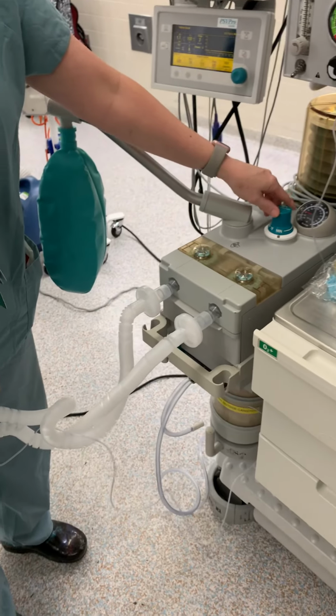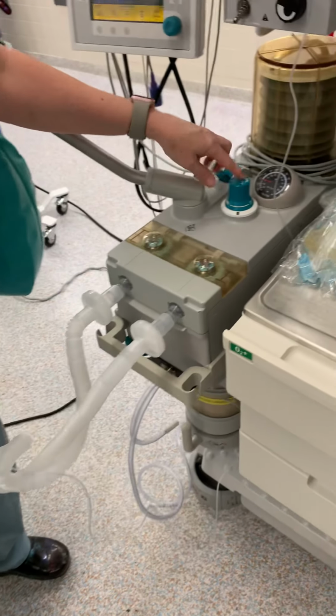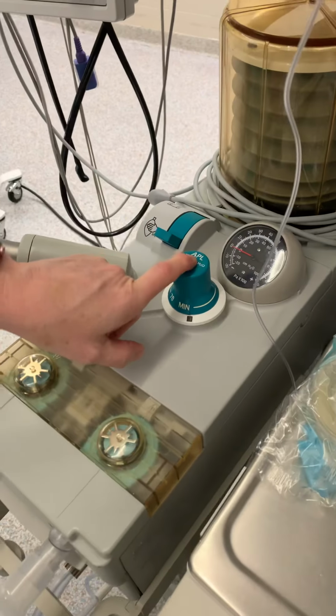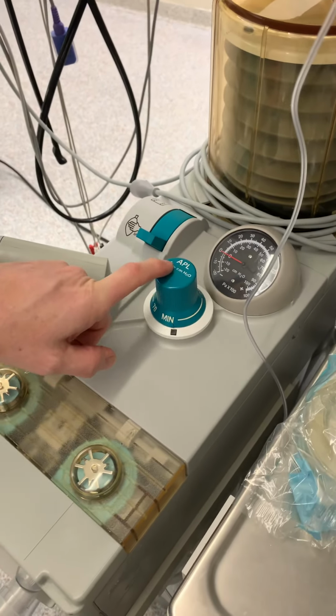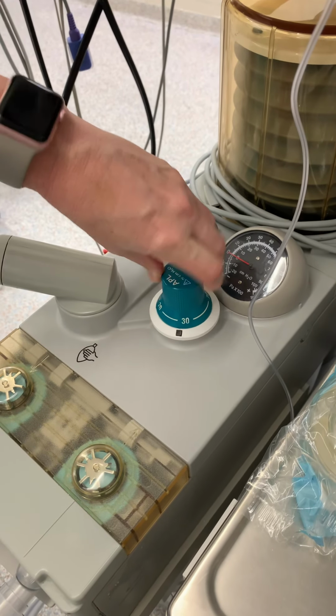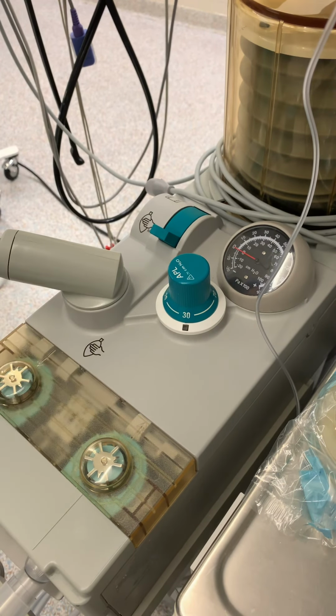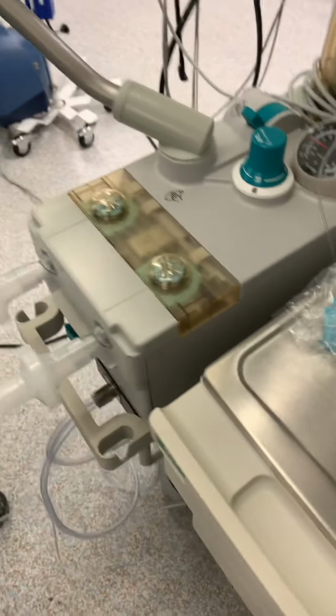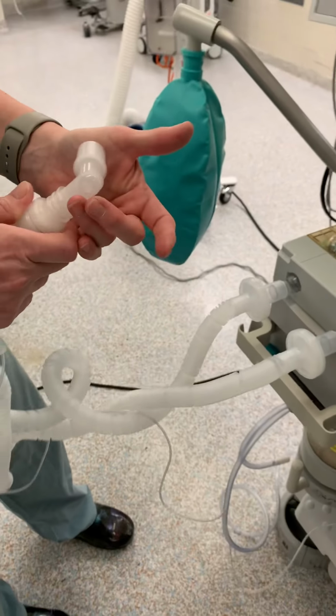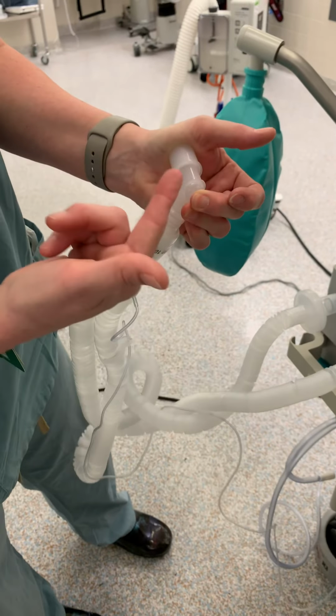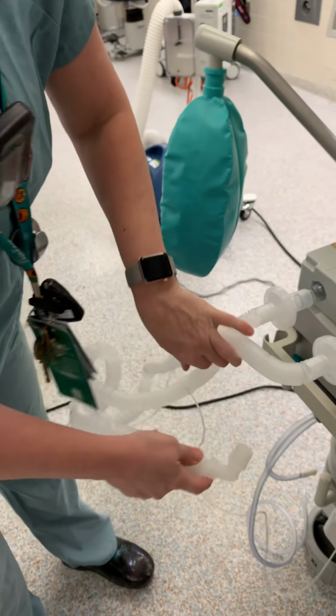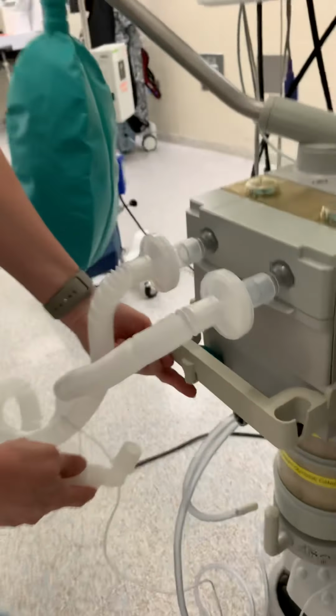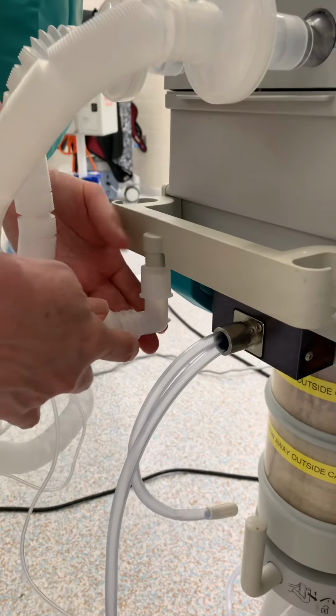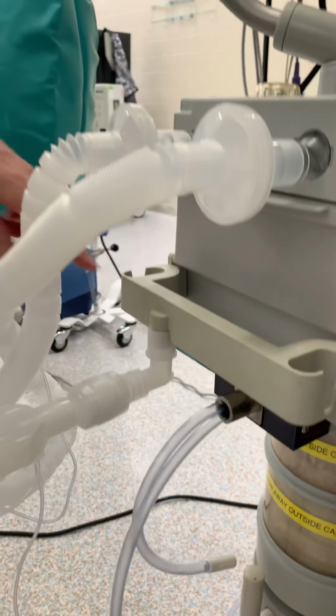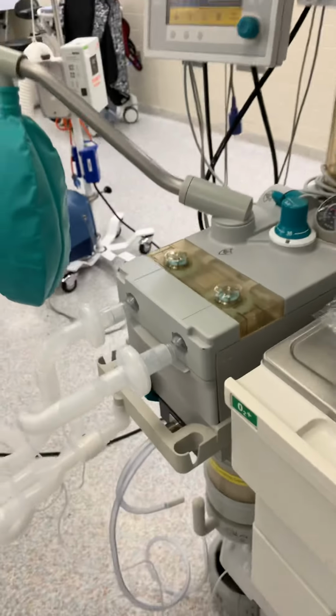So right now, we want to take your APL valve, and the APL valve says just that at the very top, APL. You want to put it on 30 centimeters of water pressure, and then you want to occlude the Y. You may see people hold it and occlude the Y, but properly done, there's a place on every machine.